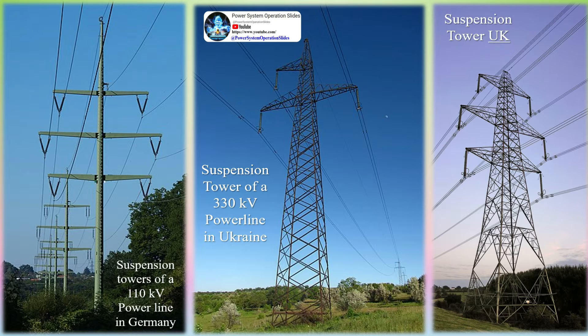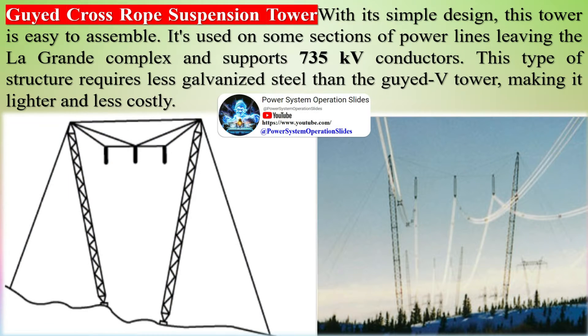Angle towers, sometimes called semi-anchor towers, must resist transverse loads induced at an angle in addition to the usual wind, ice, and broken conductor loads. Angle towers are heavier than suspension towers by necessity. The guyed cross-rope suspension tower, with its simple design, is easy to assemble. It is used on some sections of power lines leaving the La Grande complex and supports 735 kV conductors. This type requires less galvanized steel than the guyed V tower, making it lighter and less costly.